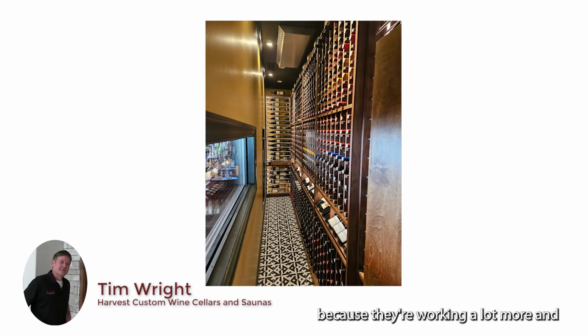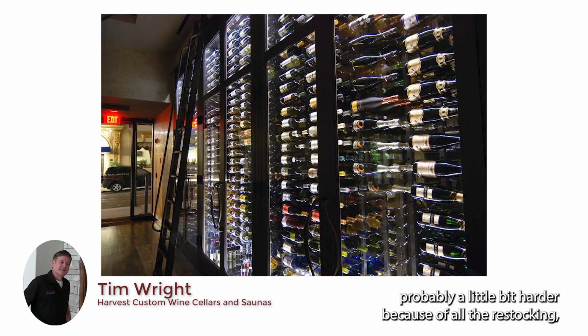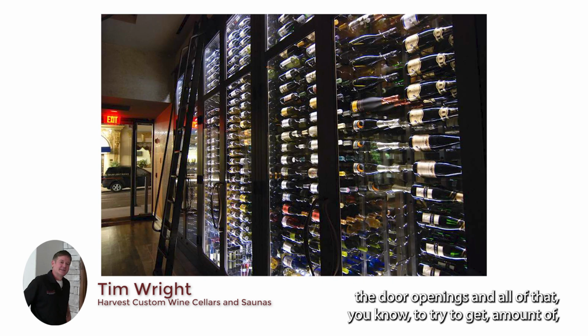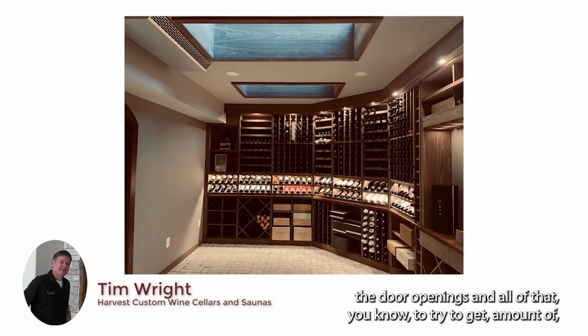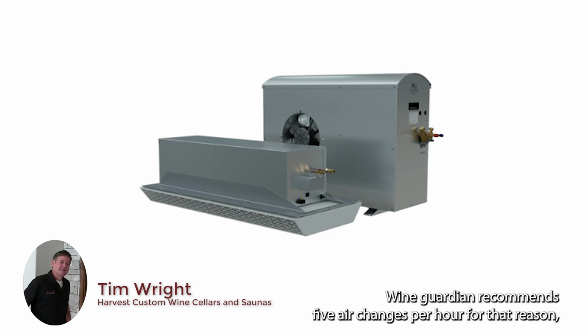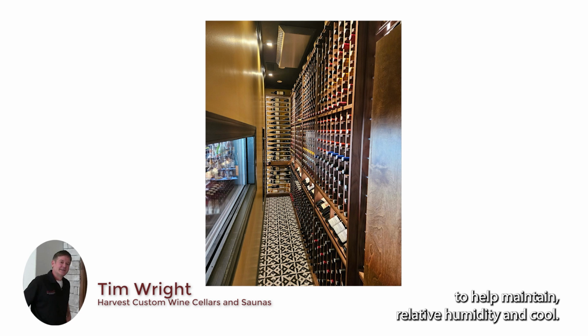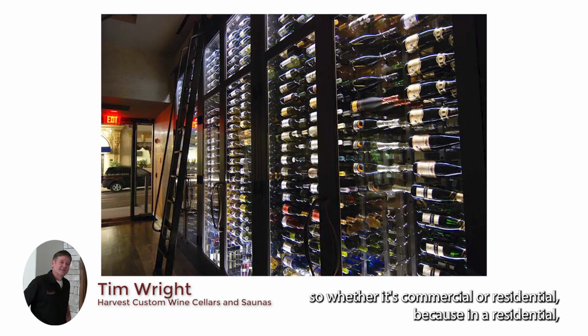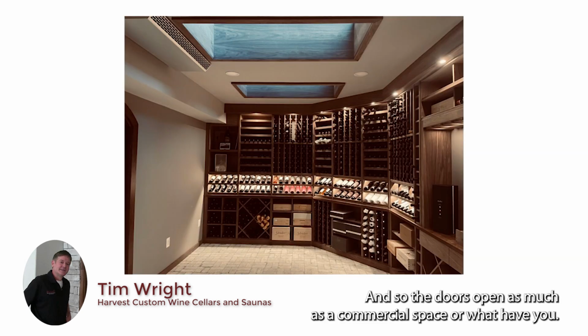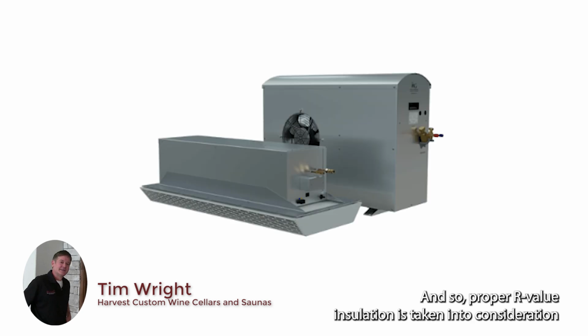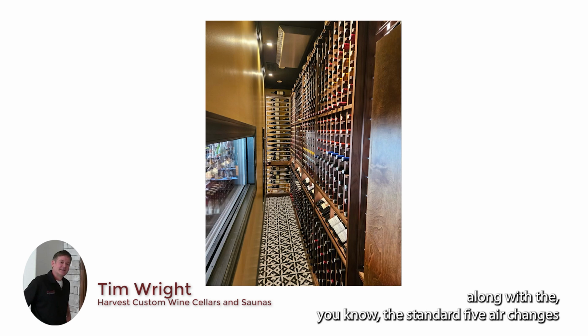It just seems to me that they're working a lot more and probably a little bit harder because of all the restocking and the door openings, to try to get the amount of air changes in there. Wine Guardian recommends 5 air changes per hour for that reason, to help maintain the relative humidity and the cooling. So whether it's commercial or residential, because in a residential wine cellar they may have a party, and so the doors open as much as a commercial space, proper R value insulation is taken into consideration along with the standard 5 air changes per hour.